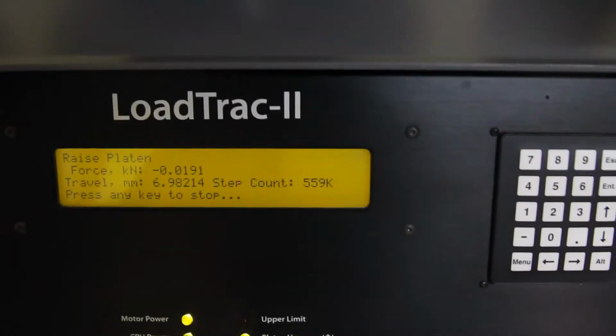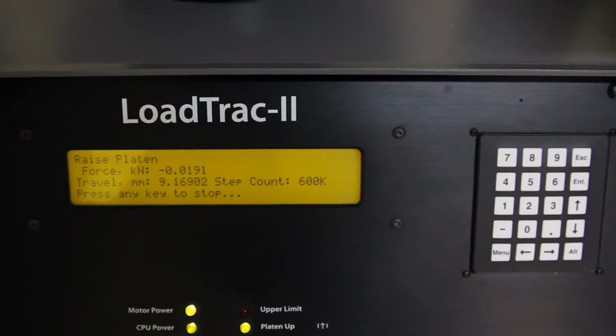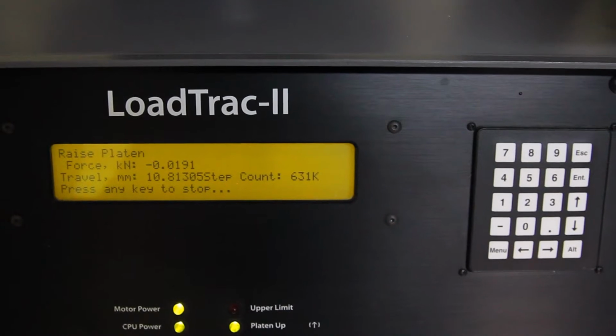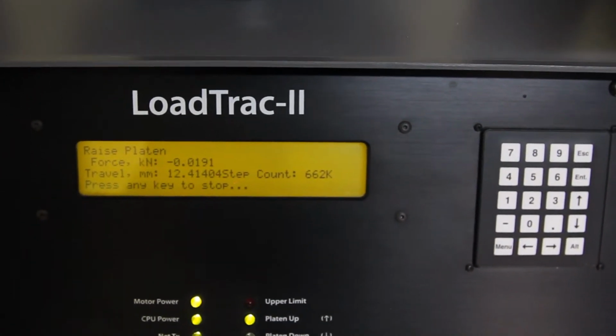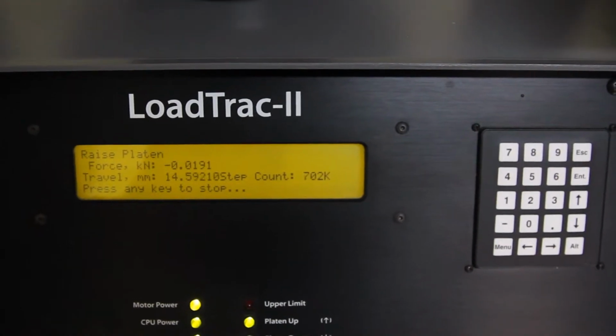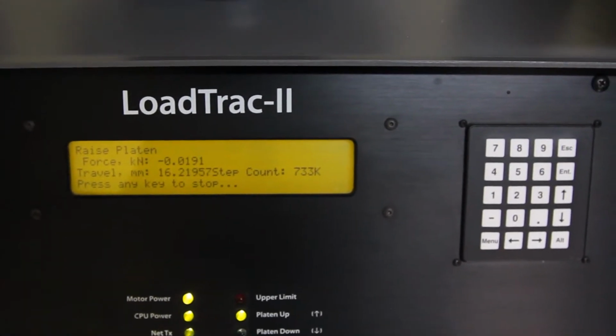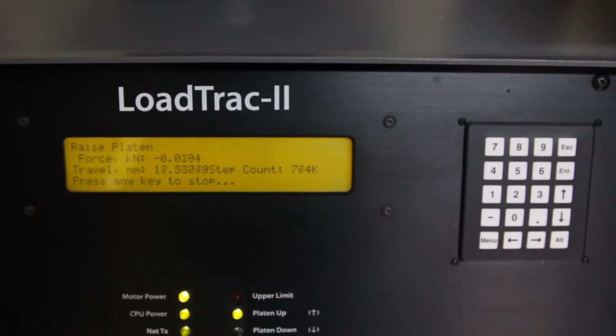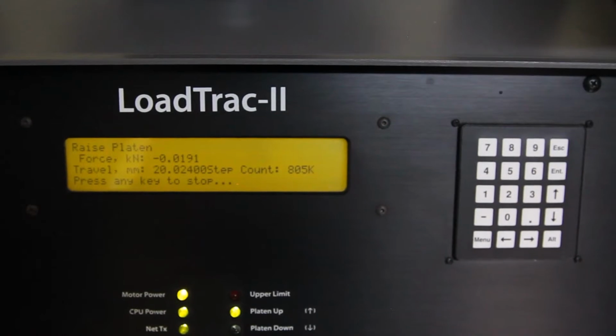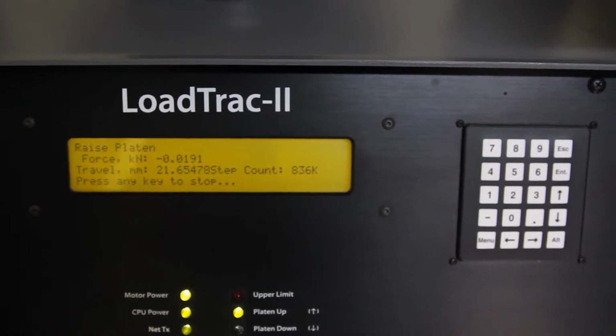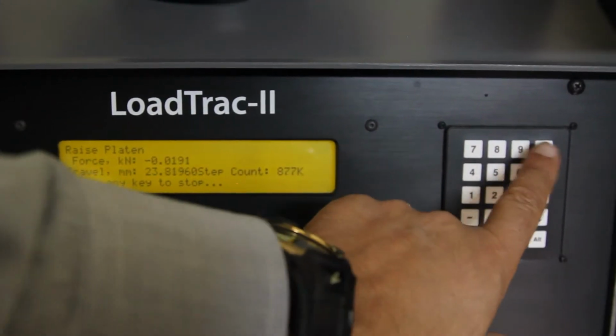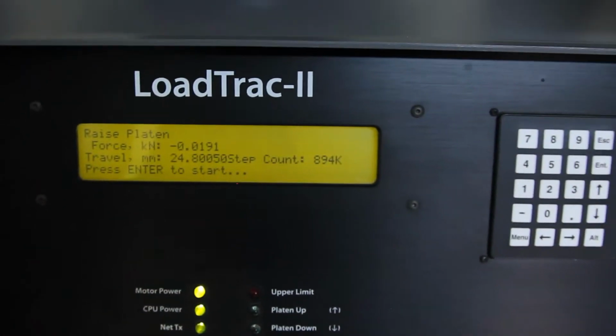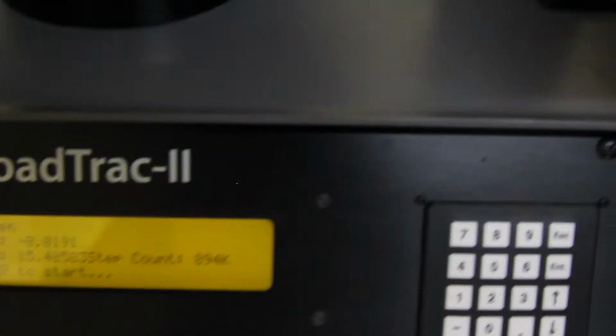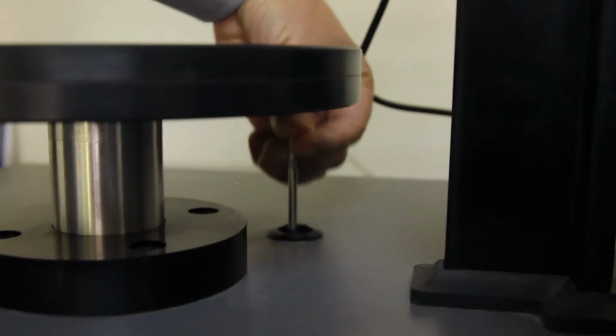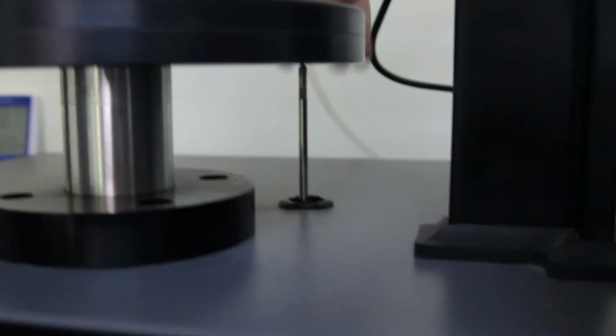And we need to do at least 4 points to do our calibration for our displacement sensor. Right now we're waiting for the platen to reach about 850, 900K, and once we reach that, then we are ready to do the calibration of our displacement sensor. So now we're going to wait, and we're about there, about 850, 860. I'm just going to press any key. So now we are ready. As you can see, the sensor is underneath the platen here, and we have a lot of range here to insert our blocks underneath so we can do our calibration.